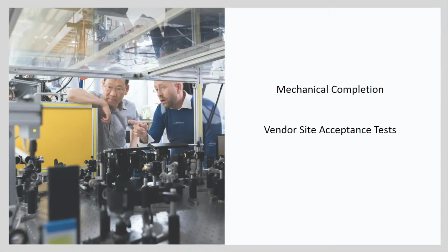So if we start with the pre-commissioning activities on site, really the first trigger that's going to take place is mechanical completion. This is the first thing to occur. And typically for electrical systems, mechanical completion takes place, so the handover from the construction team to the commissioning team, followed by the pre-commissioning that's done by the commissioning team itself. I haven't worked on too many projects where the construction team has done the electrical pre-commissioning. That's usually a commissioning team's responsibility. So then the sequence would be the systems are installed, mechanical completion takes place, so it's handed over to the commissioning team, and then the commissioning team starts to perform the electrical pre-commissioning activities.